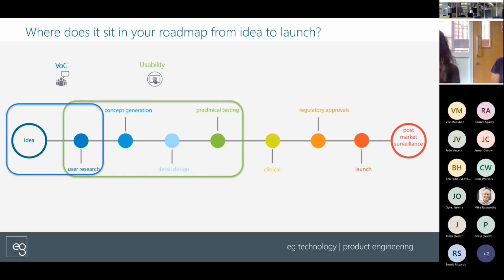And the testing and design stages are iterative. You'll test, feed that information back into the design, and so on until your design has been frozen and you're doing the more formal verification and validation stages, which is at the end of this process of usability engineering. And this overlaps with the beginning of clinical evaluation, as you're starting to prepare for your clinical evaluation, which is your ultimate validation. You'll be finishing up your usability engineering.